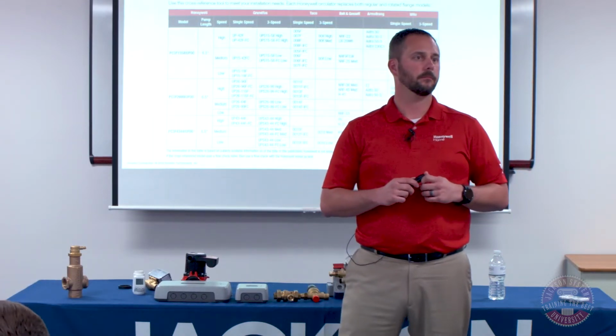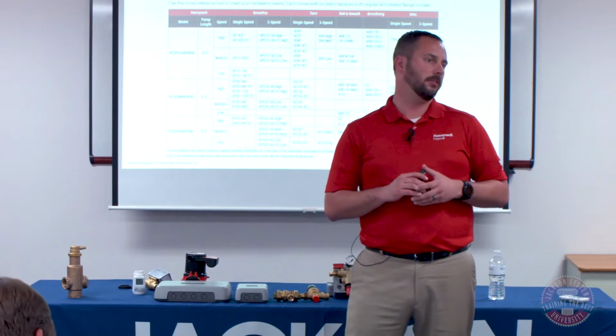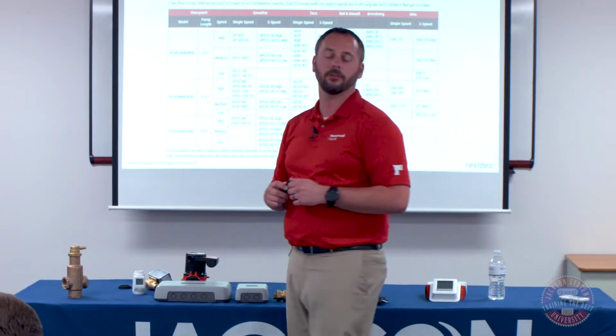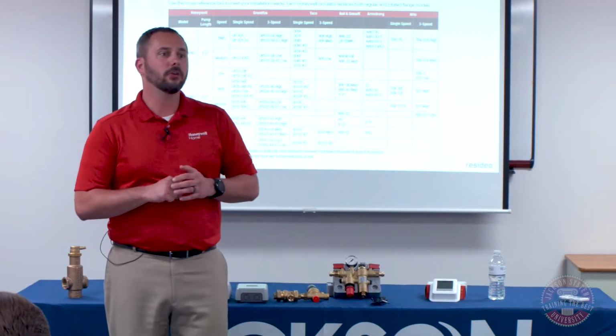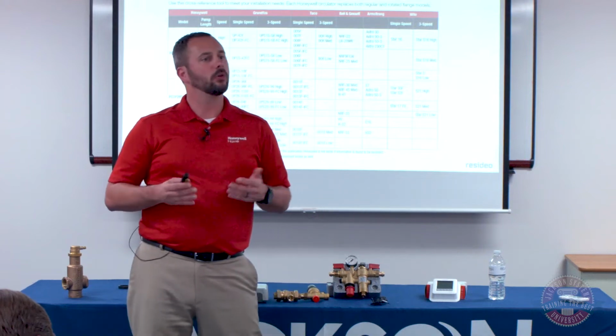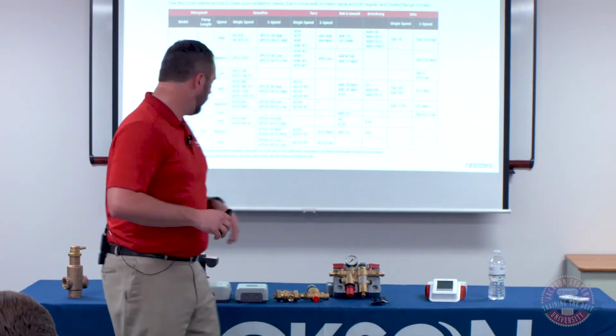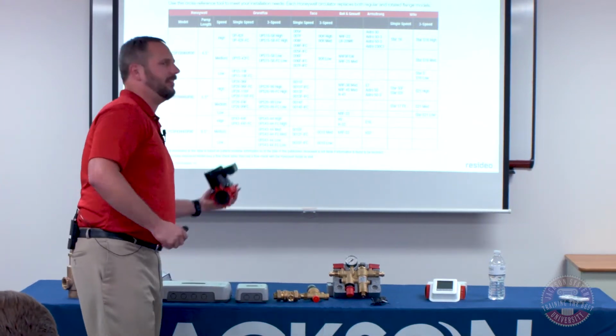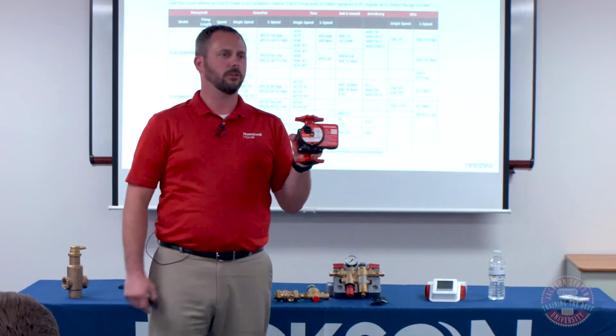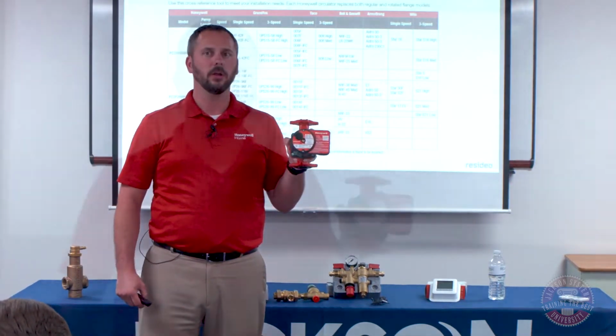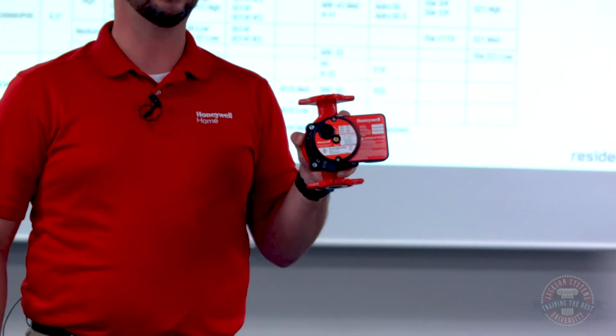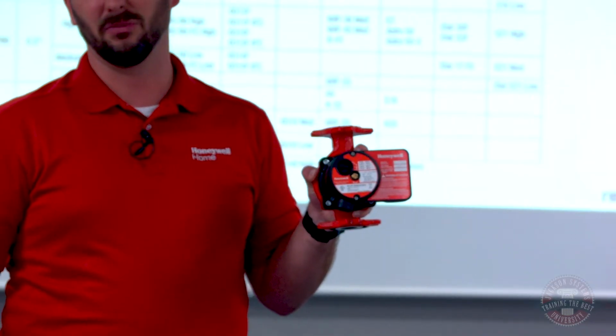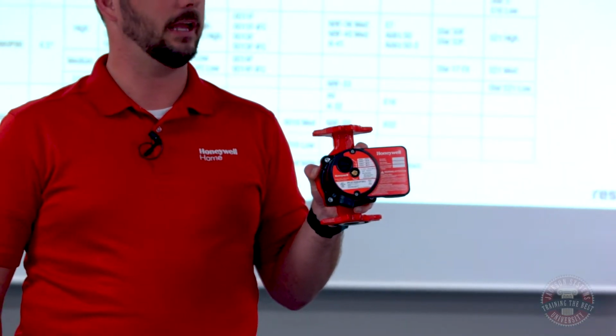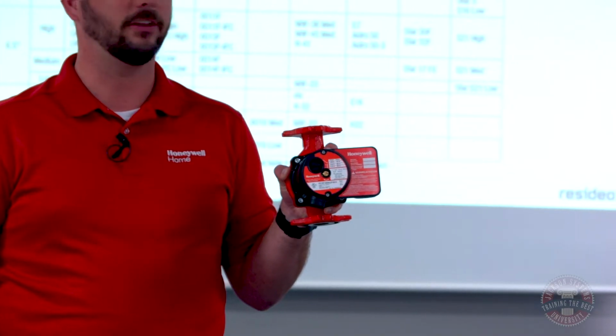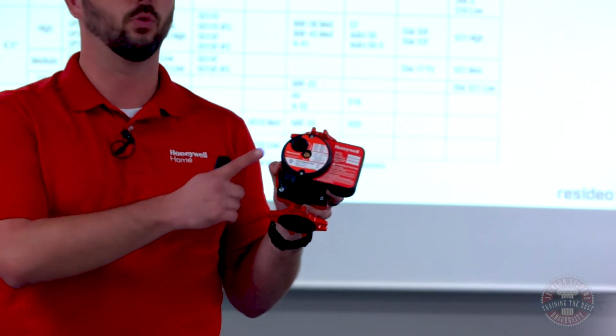Okay. And then another question from Ricardo at UEI. Are those pumps single-phase or 3-phase? These are all going to be single-phase 120-volt circulators. Good question. These are all small pumps, so when you break it down and look at the horsepower rating, the smallest one, which is most common, and I'm talking mainly about residential systems, is a 1/25th horsepower. So very, very small. The amp draw on speed 1, I believe, is 0.35 amps, like 35 watts. So these are all going to be 120-volt single-phase.